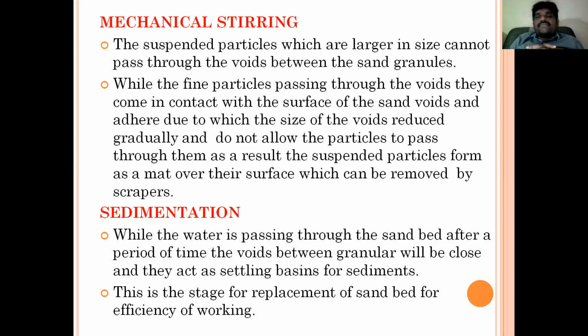like sand, the voids in between the sand granules play a vital role in this filtration. See here the first point, the suspended particles which are larger in size cannot pass through the voids between the sand granules. That means those voids are acting as filtering units.